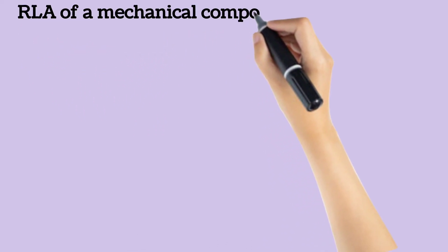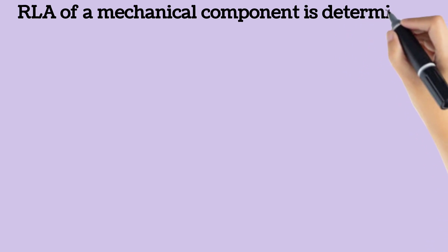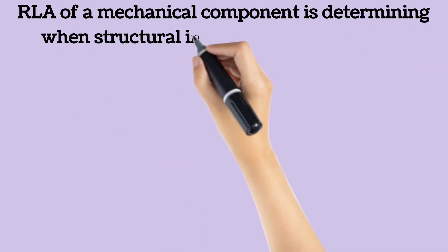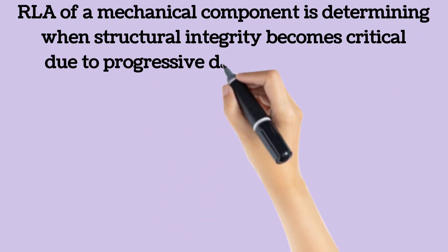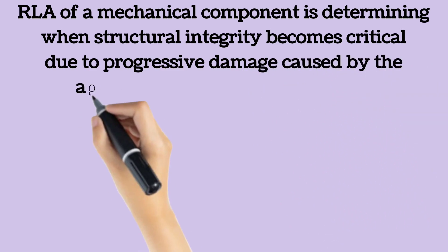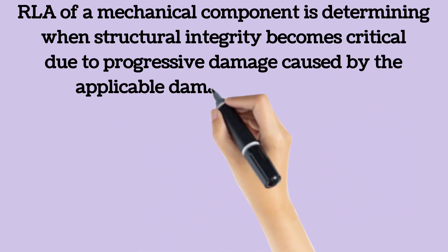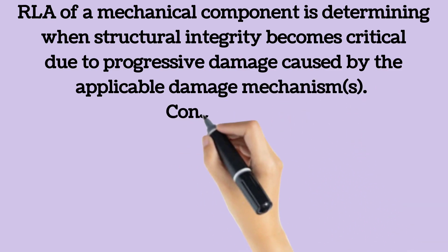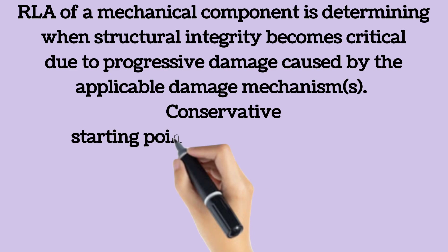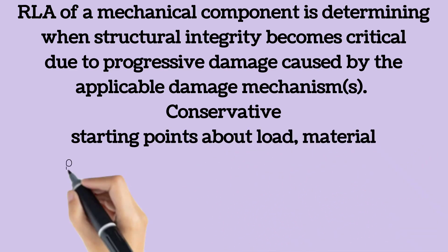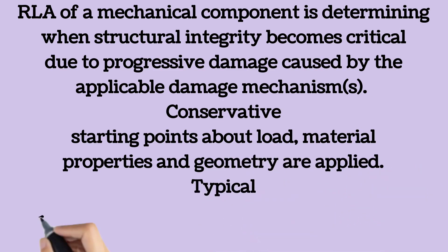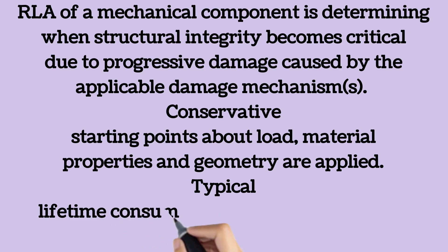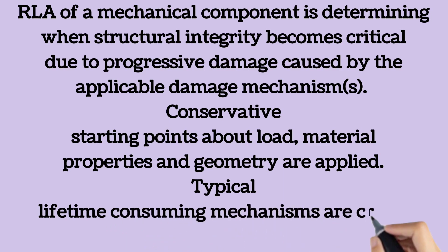The key point in determining the remaining life of a mechanical component is determining when structural integrity becomes critical due to progressive damage caused by the applicable damage mechanisms. To ensure an assessment result on the safe side, conservative starting points about load, material properties and geometry are applied. The lifetime of mechanical components is often limited due to damage mechanisms occurring during service or periods of outage. Typical lifetime-consuming mechanisms are creep, fatigue, erosion and corrosion.